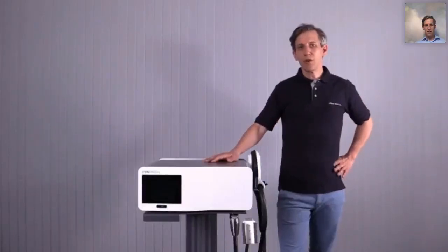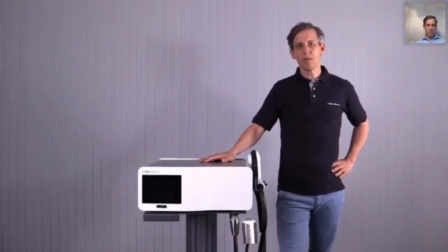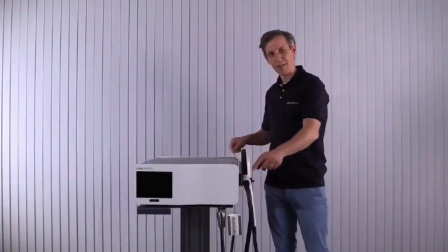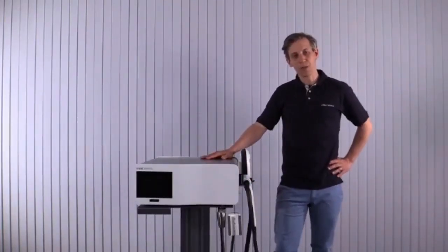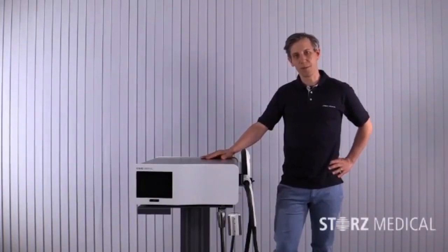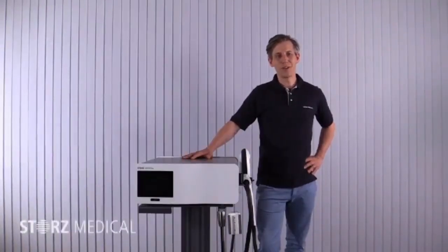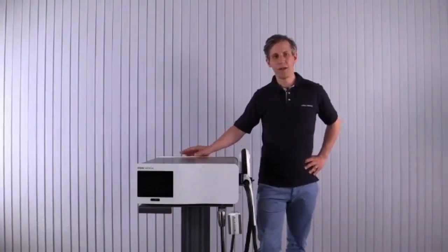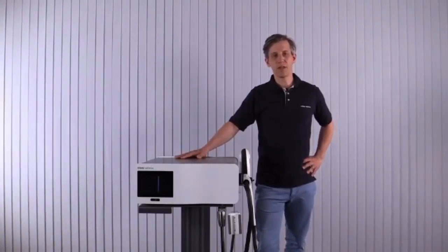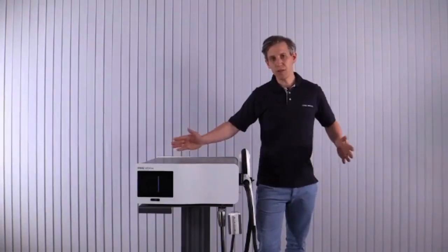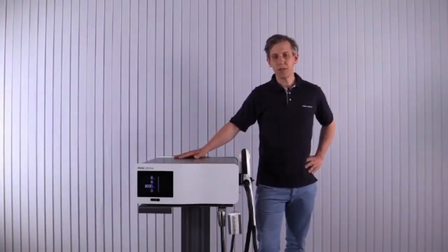In this video, I'd like to show you the main device with its accessories. And in front, we have the holding arm, which can be easily adjusted with one single knob. To get started, switch on the device at the back. The startup takes approximately 20 seconds. Please note the user is prompted to conduct a high voltage test once a day. This test checks for any interference and the energy levels.